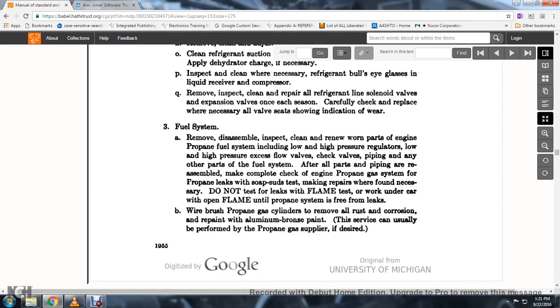3. Fuel system: remove, disassemble, inspect, clean, and renew worn parts of the engine propane system — flow valves, check valves, piping, and any other parts of the fuel system. Reassemble and make a complete check of the engine propane gas system for propane leaks using a soap suds test; make repairs as found necessary.